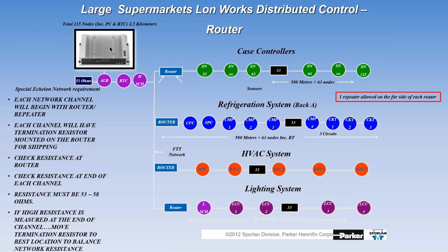If anything should happen to the data logger, the nodes sync to the real-time clock on the alarm node. If anything should happen to the alarm node, each individual node has its own countdown clock. To be truthful, if that happens, you'd lose some synchronization using the internal countdown clock, but at least they'll have some type of clock to refer to. So you have one level, a second level of redundancy, and then your final redundancy is the countdown clock on the smart node.